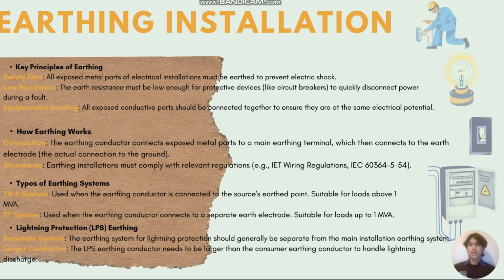For the second, how earthing works: connection and standard. For the connection, the earthing conductor connects exposed metal parts to a main earthing terminal, which then connects to the earth electrode, the actual connection to the ground. And for the standard, earthing installation must comply with relevant regulations. Examples given are the IET wiring regulations and IEC.